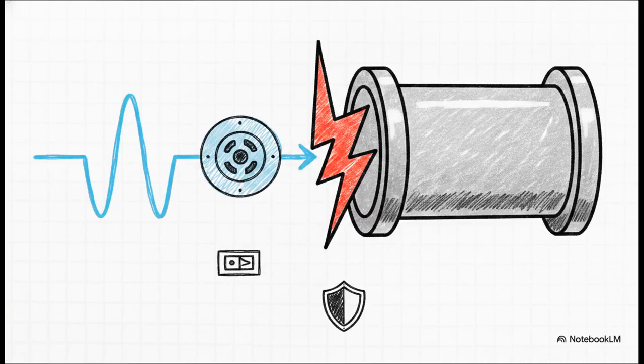The numbers really back this up. The V-contact is fantastic for switching because of its sheer precision. It's got a closing current of 2.4 kiloamps and an extremely low chopping current of half an amp or less. And that ultra-low chopping current is vital, right? Because it prevents dangerous overvoltage transients in your motors and transformers. But take a look at its interrupted current capability. It's only 400 amps. That right there is exactly why those fuses are non-negotiable for handling massive fault currents.